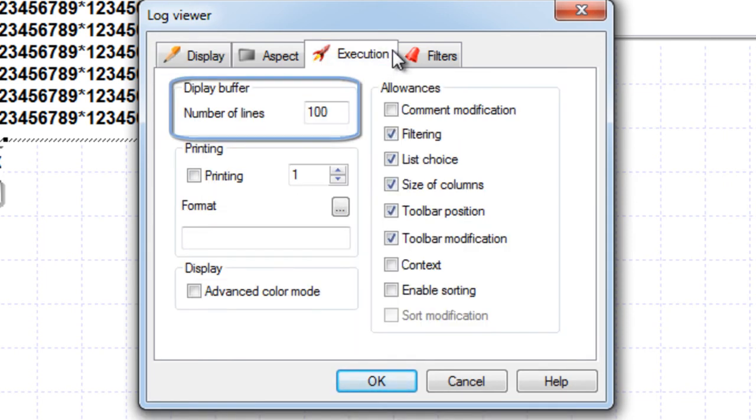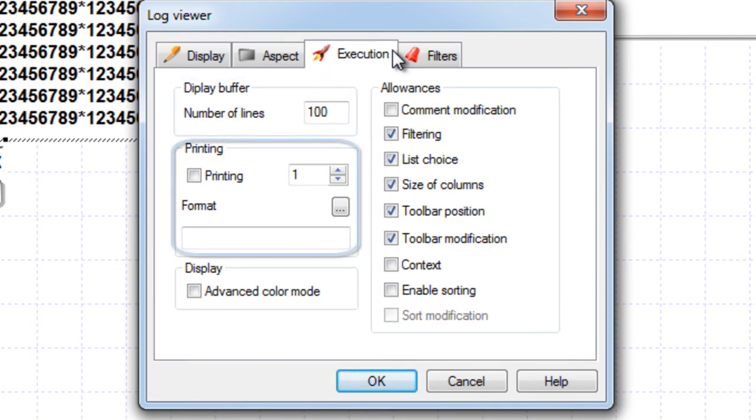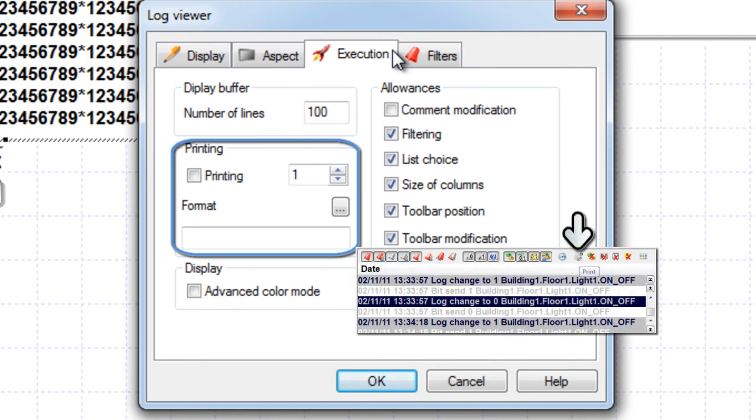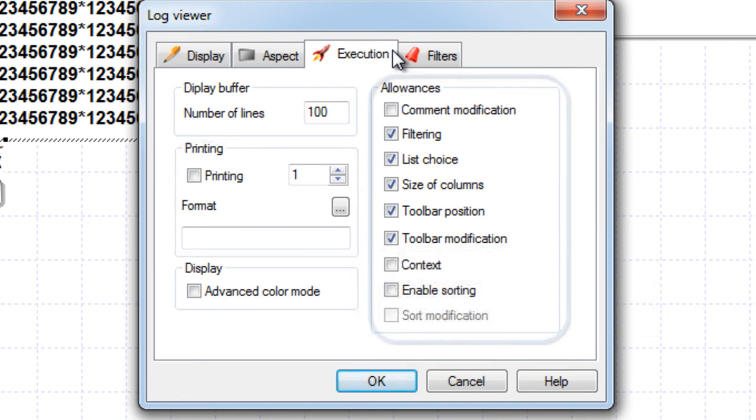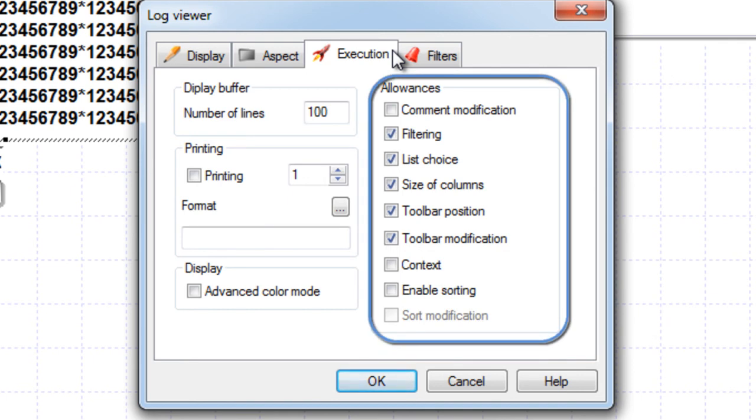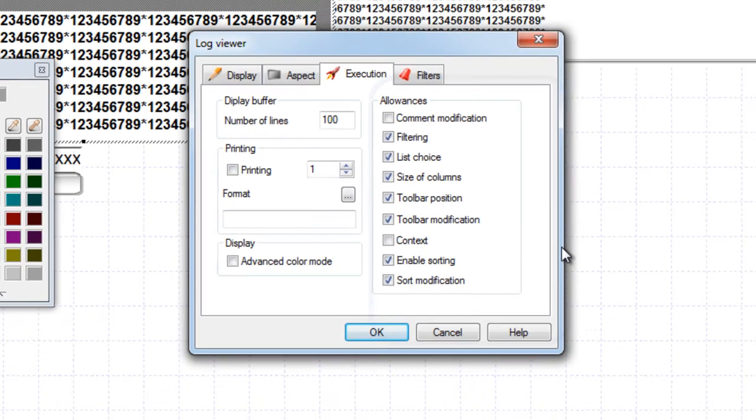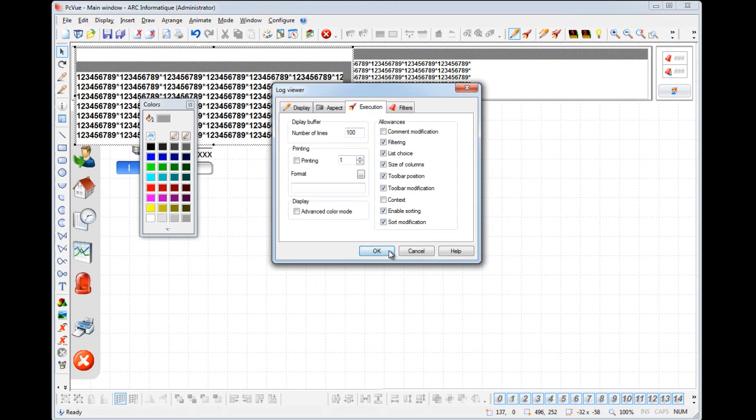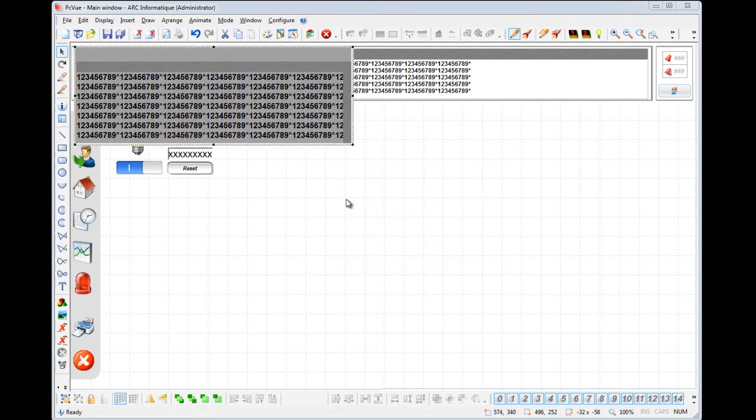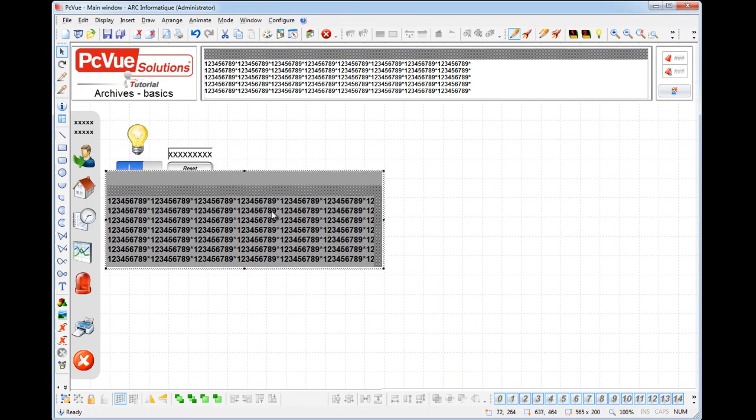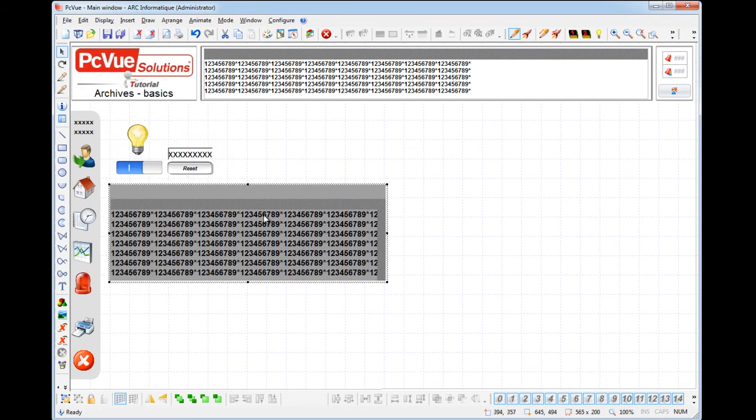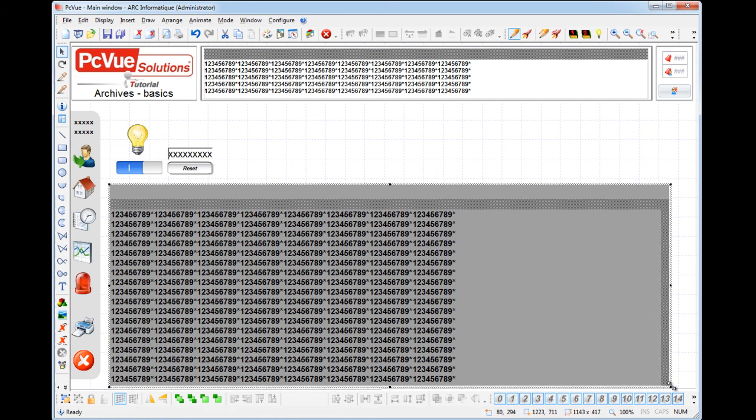From the execution tab you can select the number of lines to be displayed, authorize the operator to print the selected event by clicking the print icon in the toolbar, and select the allowances or authorizations that the operators are permitted at runtime. For example you can tick the enable sorting to have the list of events sorted according to the content of a particular column. The sort modification is then automatically ticked to allow the user to change the sort column and direction. Click OK to validate and you can resize and move the log viewer anywhere in your mimic as any other object.